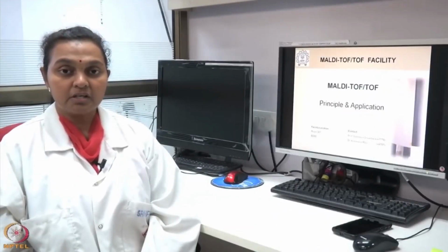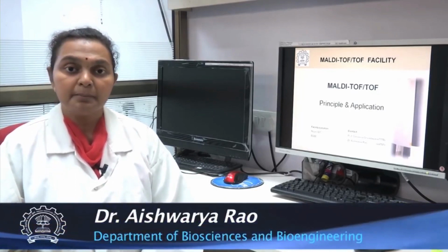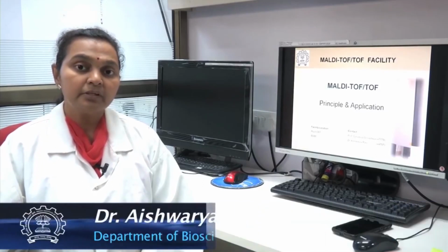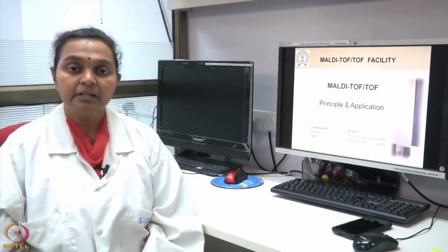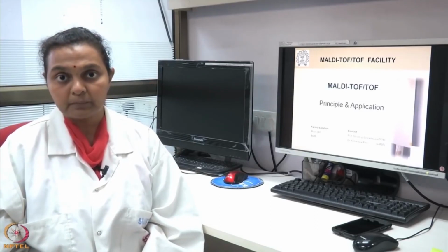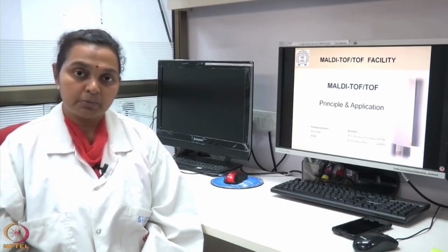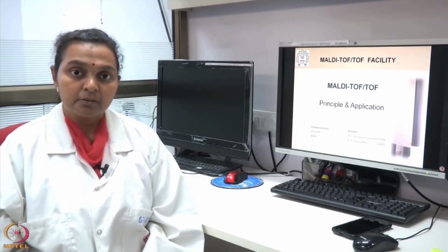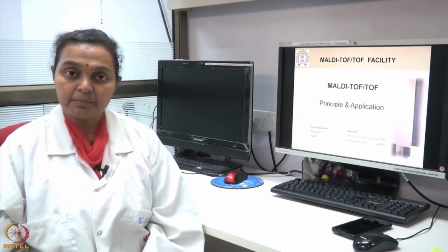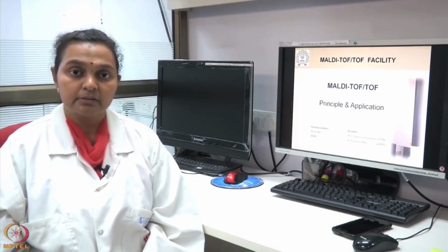So, let us start our first demonstration on MALDI-TOF-TOF. Hello, I am Dr. Aishwarya Rao, in charge of the MALDI facility in Professor Sanjeeva Srivastava's lab. MALDI is one such instrument which is used as a mass spectrometer. The instrument that you can see behind me is a MALDI-TOF-TOF, called the Autoflex Speed, made by Bruker. The ionization source in this instrument is a smart beam laser, which is used to ionize the samples. The mass analyzer in this particular instrument is called the time of flight.